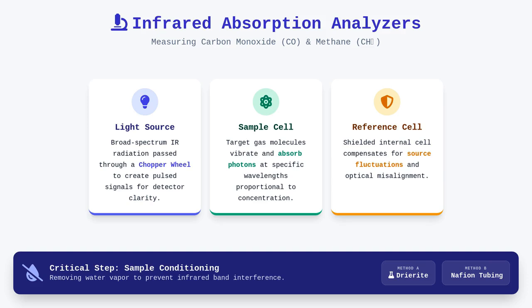A chopper wheel is essential in this configuration, as it periodically interrupts the infrared beam to create a pulsed signal, allowing the detector to distinguish between the static light source and the dynamic absorption changes. An internal reference cell, shielded from the sample gas, helps the system compensate for fluctuations in light source intensity or optical misalignment over time. One critical aspect of this technology is sample conditioning.